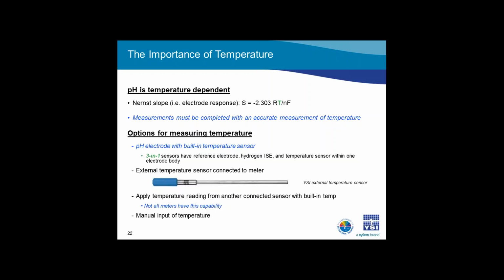The last option would be to manually input your temperature value during calibration and measurement. I would only recommend this option if you are using a temperature-controlled bath where you're keeping the temperatures constant for both calibration and measurement. If you expect the temperature to vary from calibration and during measurements, it's best to supply the instrument with a temperature measurement so proper compensation can be carried out consistently and accurately.